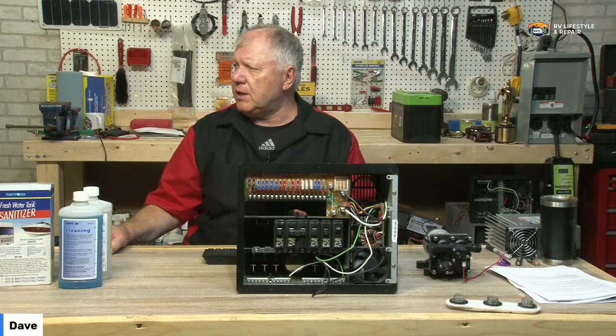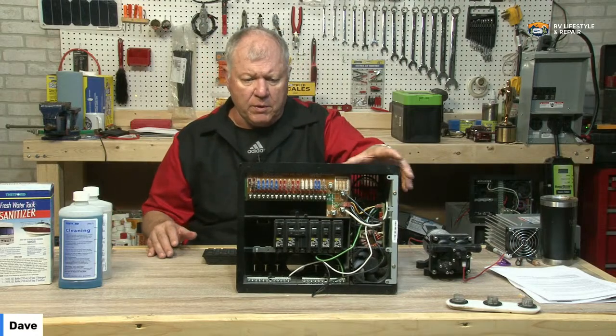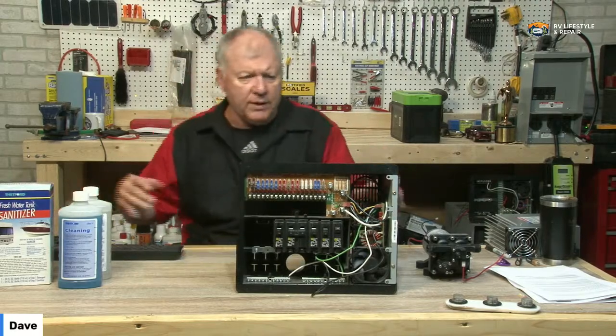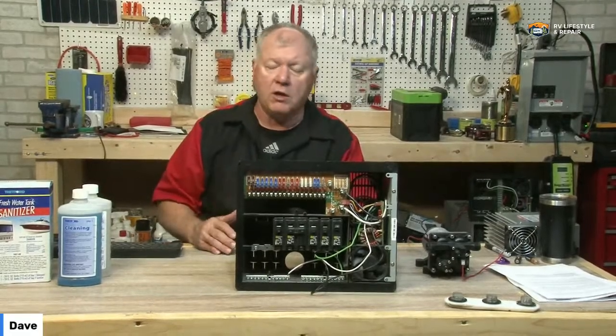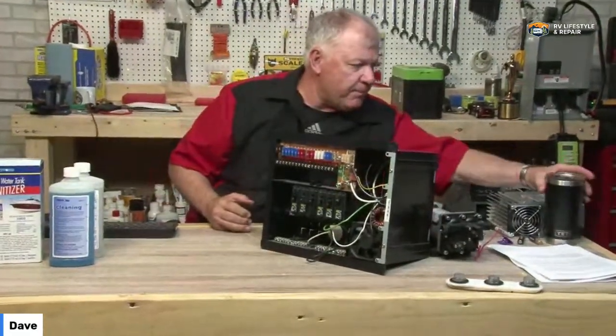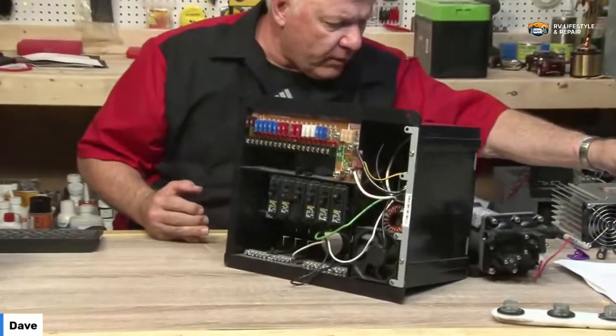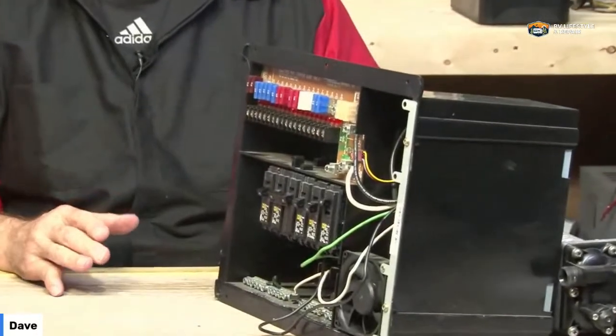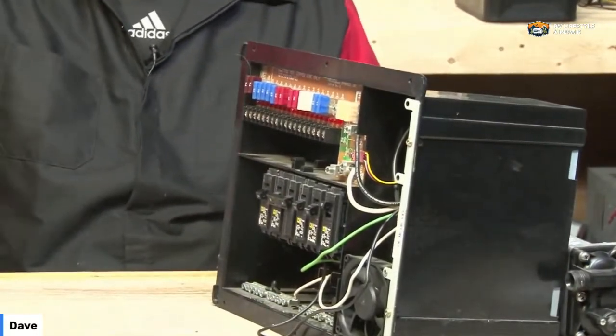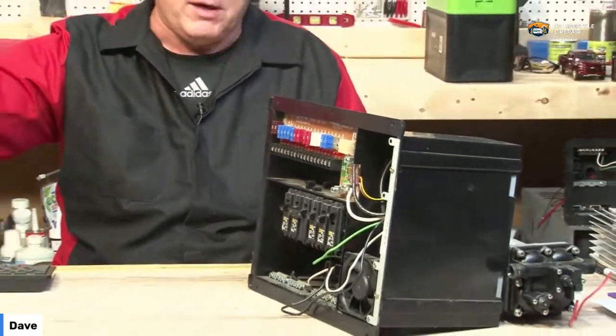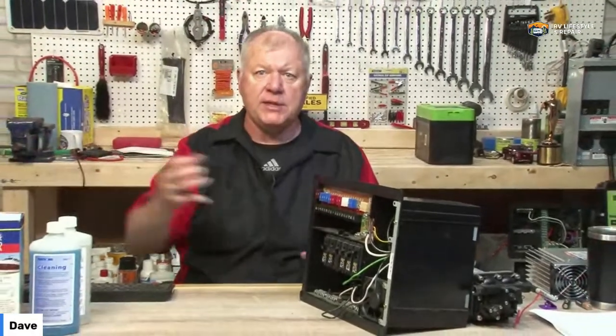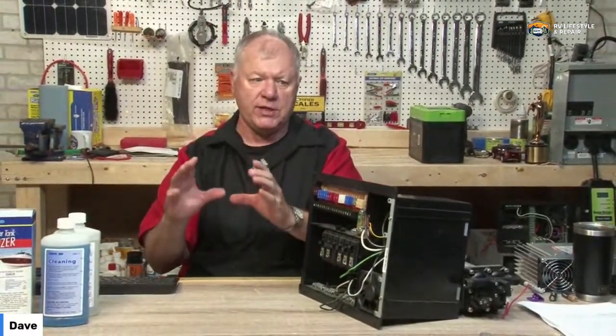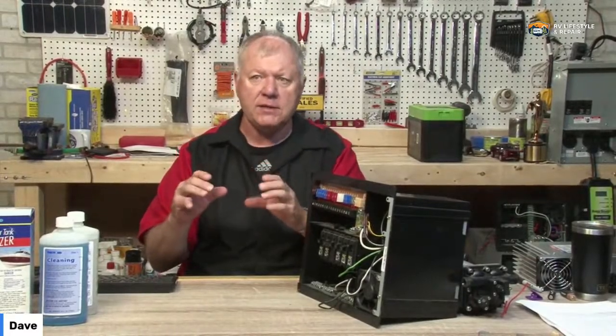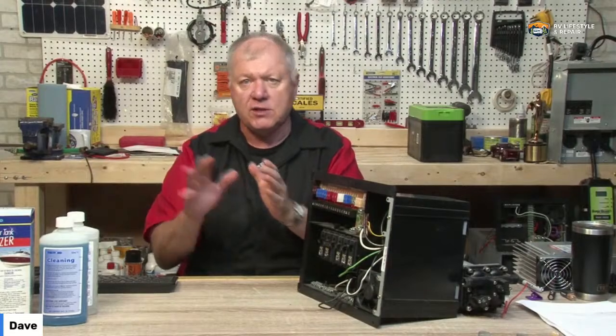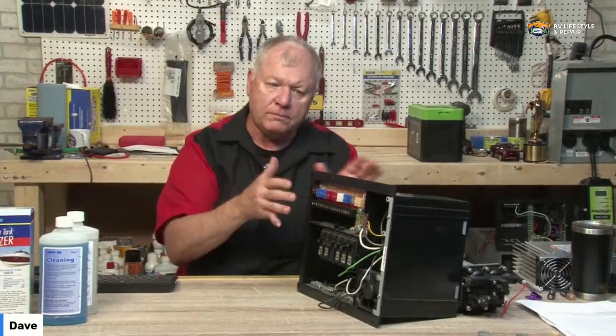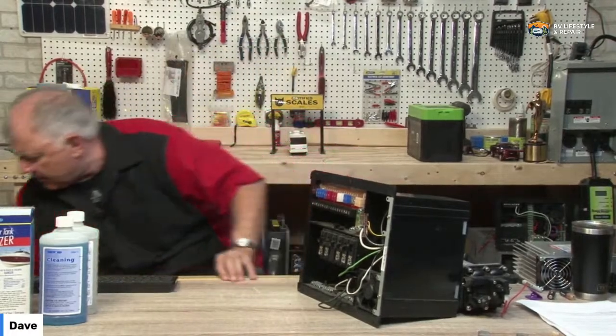Okay, so it looks to me like you've got this system right here. Basically, shoreline power comes in, and you also have what's called an automatic transfer switch. So when you hook up to a campground pedestal on a 30 amp service, it comes into this box, the automatic transfer switch, or ATS box. That box is designed to sense whether your generator is running or your shoreline power has got power coming in.